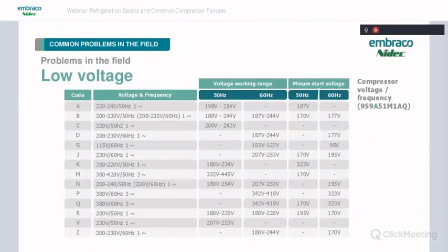So we also see a problem with low voltage in the field. A lot of times in commercial environments, you see where you might have had a dedicated circuit or a piece of equipment on one circuit, and then another piece of equipment was added. Then all of a sudden you get startability issues. This slide just shows the minimum guaranteed start voltage. We use the G code, which is 115 volt. As you can see, the minimum start voltage is 98 volts.